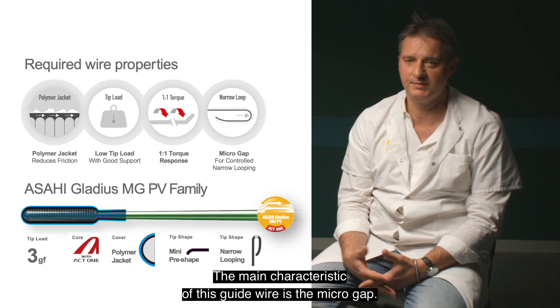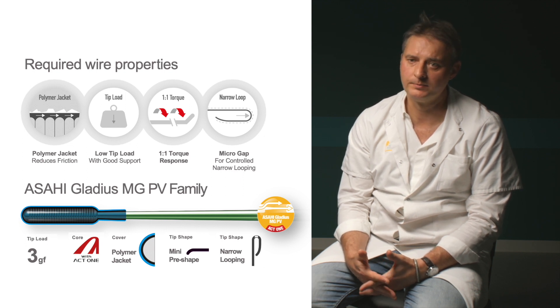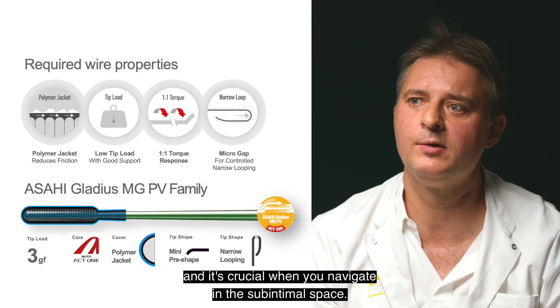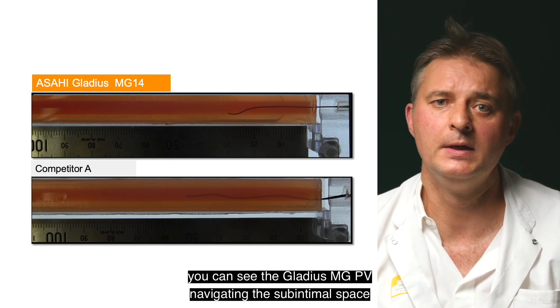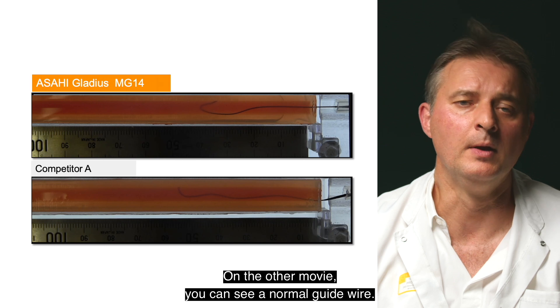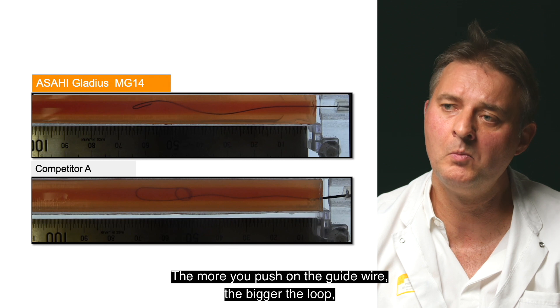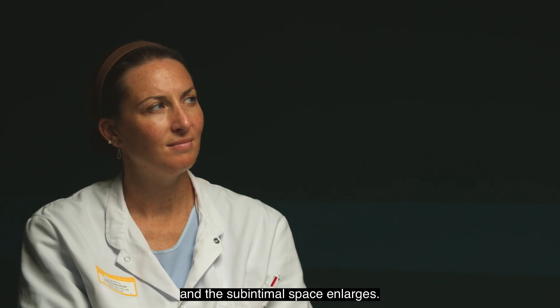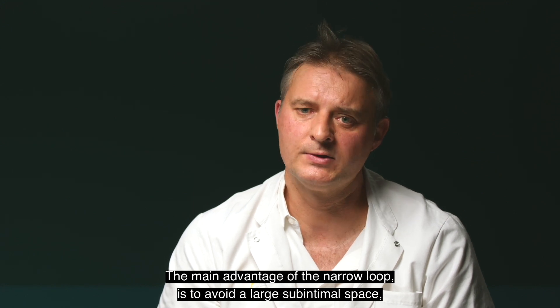The main characteristic of this guide wire is the micro-gap. This micro-gap allows a narrow loop to form. This narrow loop creates a small subintimal space, which is very crucial when you navigate in the sub-intimal space. You can see the Gladius MGPV navigating in the sub-intimal space with the smallest intimal space possible. With a normal guide wire, the more you push, the bigger the loop becomes, and the sub-intimal space gets larger and larger.